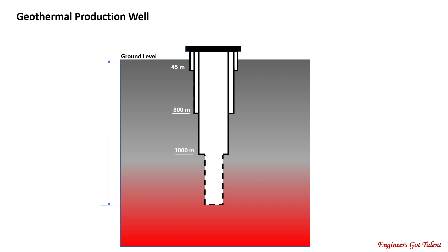First up is the geothermal production well. Geologists pick the right spot to drill a production well based on pressures and temperatures that are potential to become a geothermal reservoir. The production well conducts geothermal fluid from the reservoir to the surface. It has a set of casings made of carbon steel pipes set and cemented inside the drilled hole. The conductor pipe is driven or hammered to the ground down to 45 meters to protect the well from loose near-surface unconsolidated soil and rocks, and to prevent the infiltration of groundwater and rainwater into the well. Next is the surface casing which isolates the freshwater aquifers. It is cemented in place and provides protection in case of a well blowout.